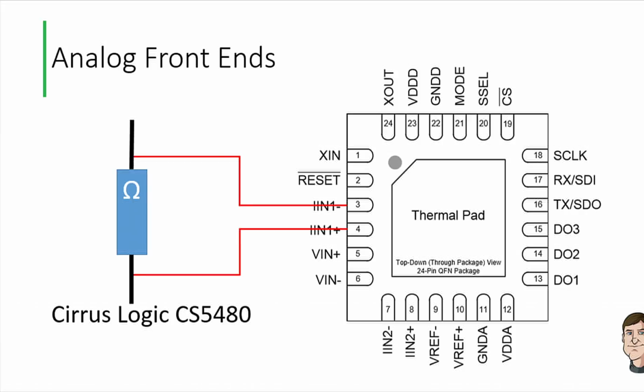What we learned is that these inputs are just ADCs in themselves. They're differential ADCs. The reference designs we used when creating the circuit had a couple of different options for current sensing. The one we went with was a shunt resistor, so you put a really low but fixed value in the current line. All the current passes through a 0.005 ohm resistor, and the ADC measures the voltage difference on one side versus the other side of that resistor. That equates to how much current's flowing through there, because of Ohm's law. Because it's such a low resistance, there's hardly any heat being dissipated by the device, and it was also very low cost. So that's why we went with that in our device.